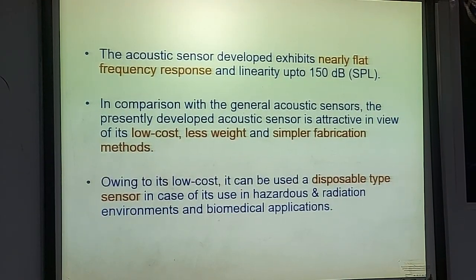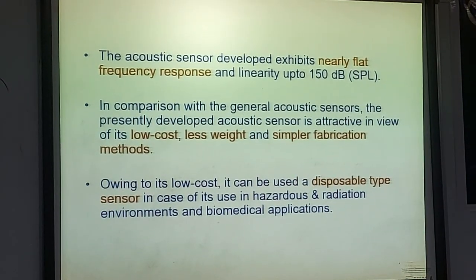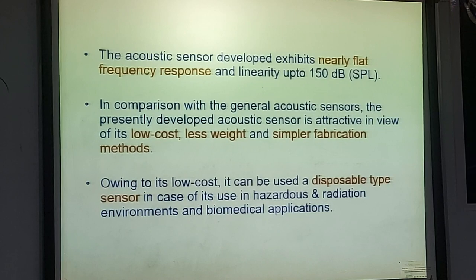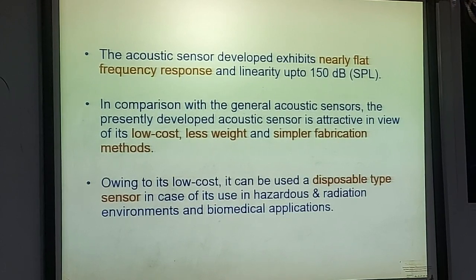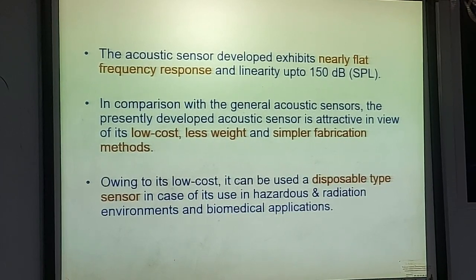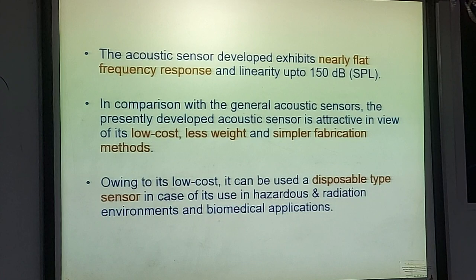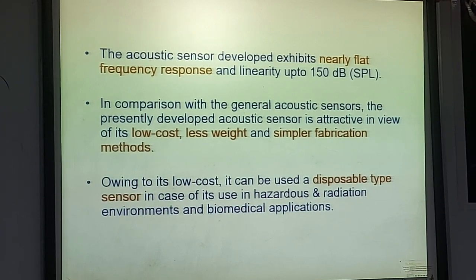The acoustic sensor developed exhibits a nearly flat frequency response and linearity up to 150 dB sound pressure level. Compared with general acoustic sensors, the presently developed sensor is attractive due to low cost, less weight, and simpler fabrication methods. Being low cost, it can be used as a disposable sensor for hazardous and radiation environments, as well as medical applications.